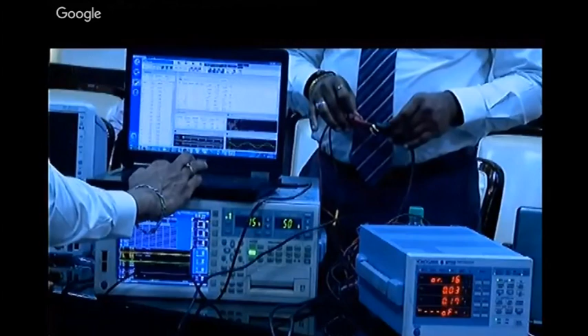And you can see all the harmonics till the 50th order also here, as a bar graph in waveform mode, right click to select bar graph. You can see the value changing also - voltage harmonics, and current will come here too, showing all the harmonics.